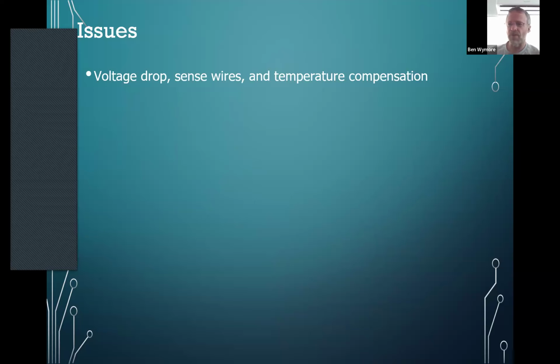Copper wire is not a perfect conductor. As you shove more and more current through the wire, it can't all pass through that diameter easily, and the less copper you have, the more resistive the wire is. If I had a wire of infinite size, everything could flow through nicely. But if I try to push too much current through a wire that's too small, much of the current is consumed as heat, so the voltage at the end of the wire isn't the same as at the source.